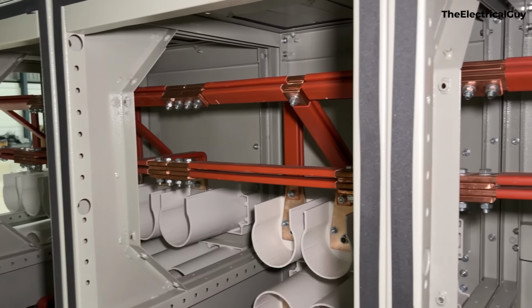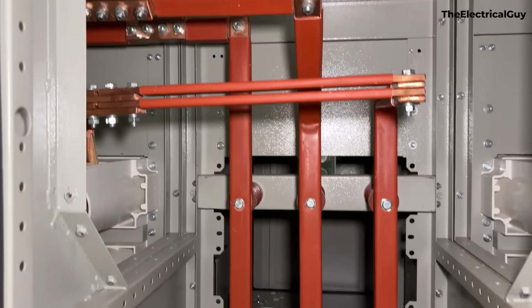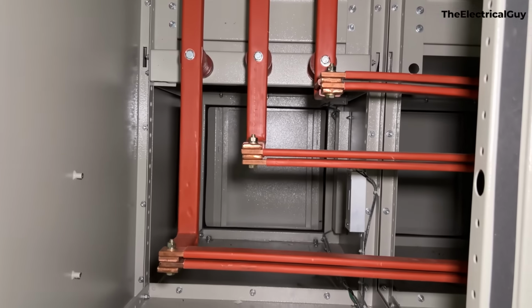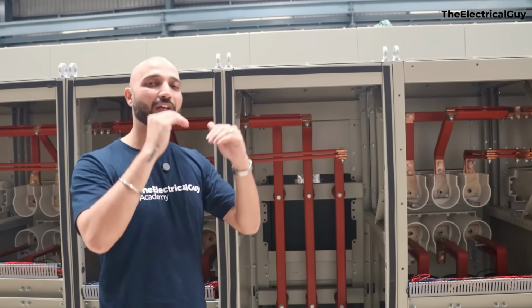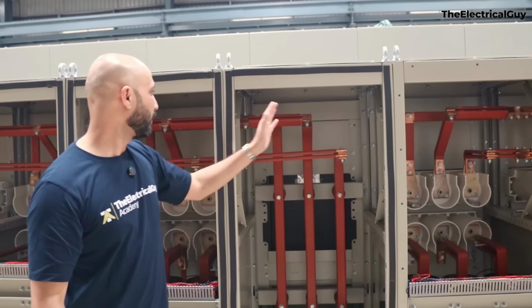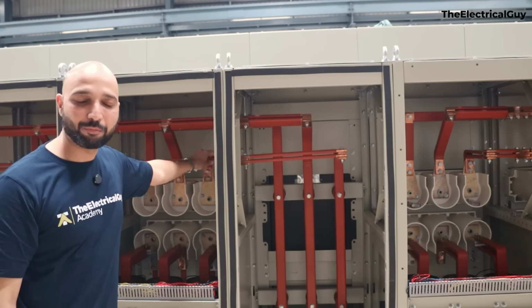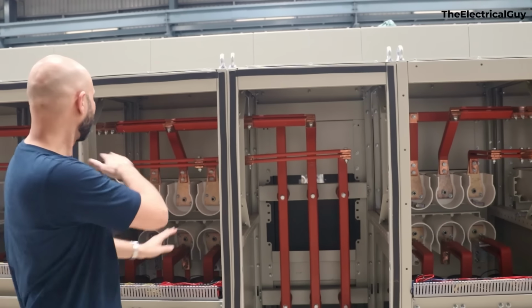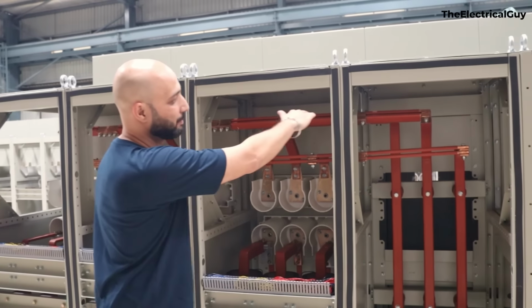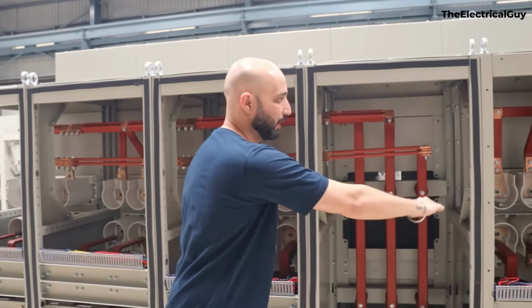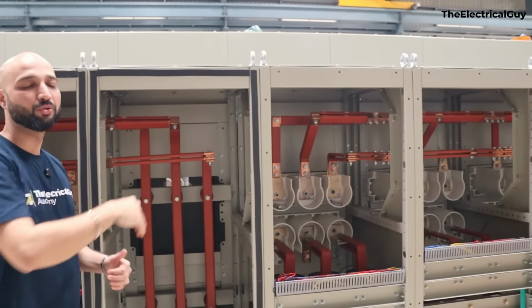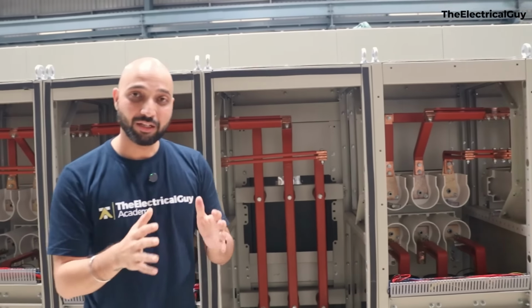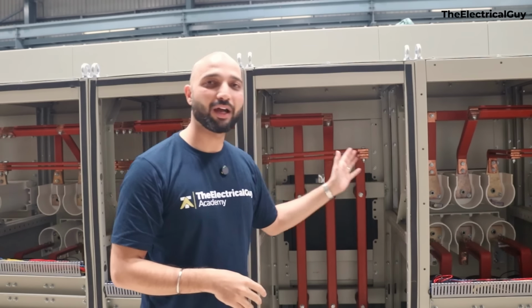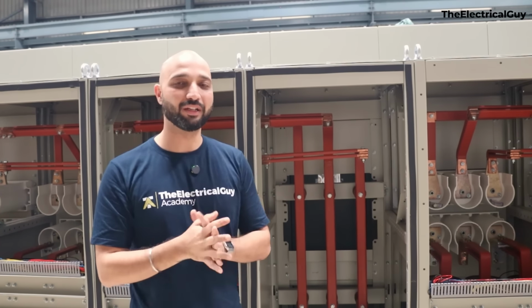You will see we don't have any breaker, we don't have any VTs, don't have any CTs, no relays, no meters, nothing. It's just helping us in raising the height of the bus bar. Once the height is raised, you can see we have connected the second bus bar to this one. So it's now a series connection. You can see the bus bars are coming like this, going down, again horizontal, going up, and then connecting to the main panel that we have. And that is the very reason why we need bus riser panel. You can see bus coupler and bus riser. That's the whole reason why we have the bus riser panel.